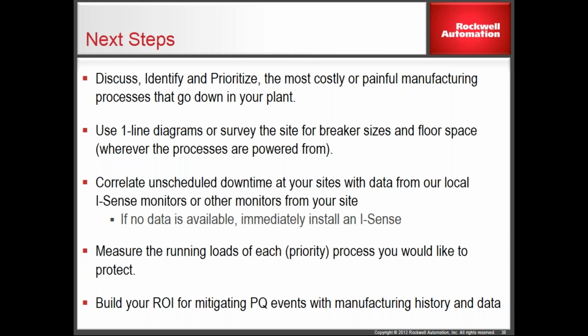So what that means is, for startup currents, I don't have to oversize the disk. I size it to the running load. So clamp a meter on, measure your running load. Don't just go by what size that breaker is. All right? And now we're going to be able to get the cost of that solution down as low as possible by actually measuring those loads.